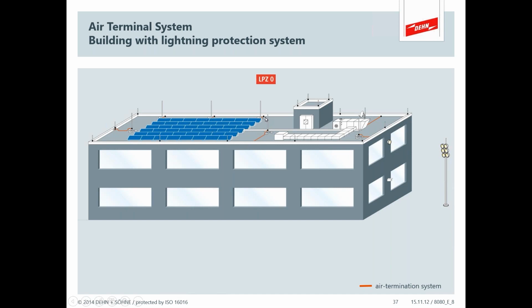So the concept is simultaneous sort of solutions. You have to do all five, but you can't just start bonding everything together, or you are inviting trouble into your air chiller. And we've seen that with customers that had used air terminals on something that looks like an air chiller like this. I guess they obeyed the standard, but what they didn't obey was separation. So now that structure that you want to protect is now part of the lightning path.